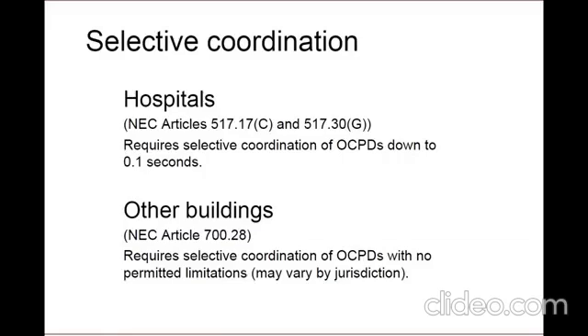Both Article 517 and 700 require selective coordination. I think Dana just talked about this, but NEC 700 emergency system selective coordination requirements do not permit any period cutoff. 517.30(G) permits faults to occur up to 0.1 seconds. Selective coordination then applies for faults that extend beyond 0.1 seconds.